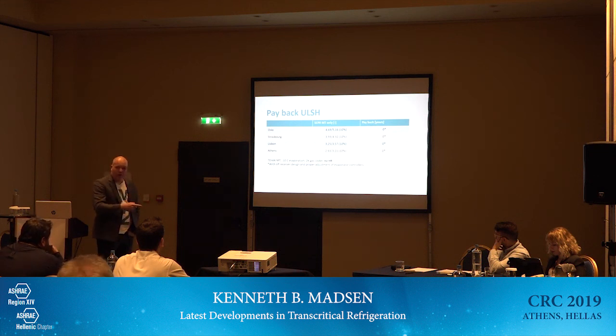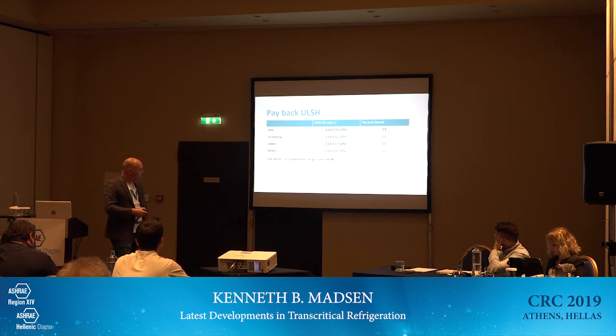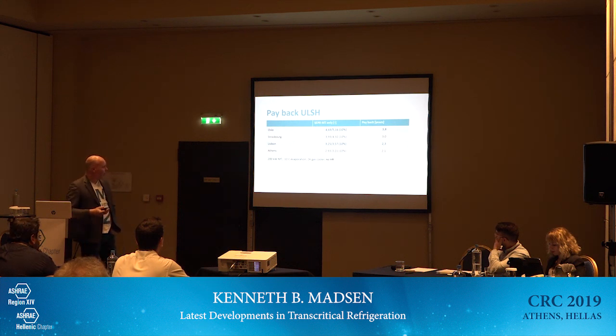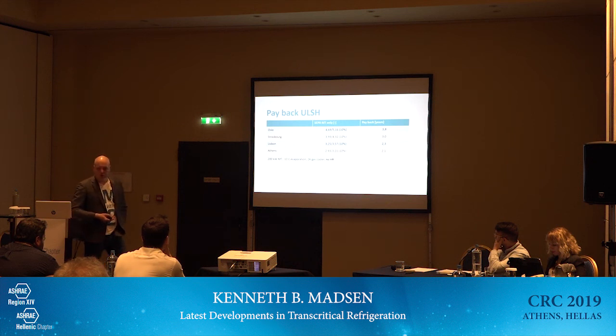Payback time on the small racks, since we're using this receiver construction, which is standard, we're not having any extra cost on it. If we move to bigger racks, you can see it's 200 kilowatts. Then you can see we get paybacks in the order of, let's say, 2 to 4 years, depending on where we are. The difference in payback is because it is basically more expensive to operate the refrigeration system in Athens than it is in Norway. So therefore there's a little bit more to work with for the payback in these.